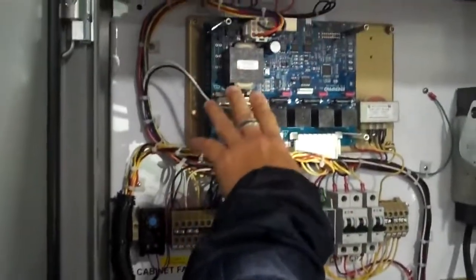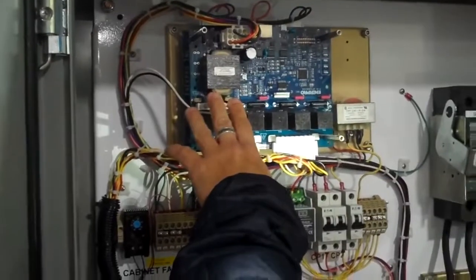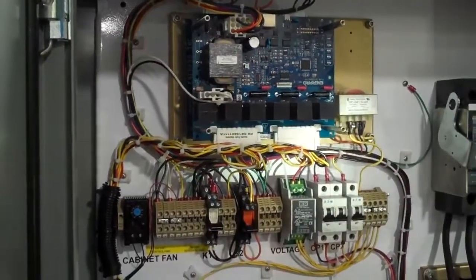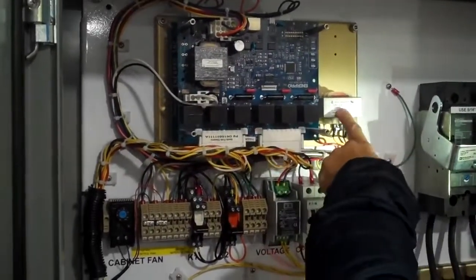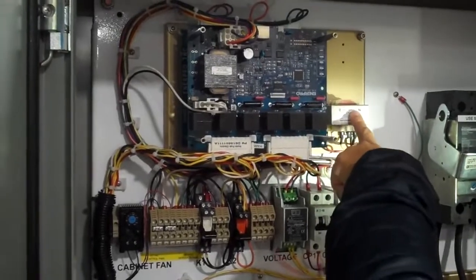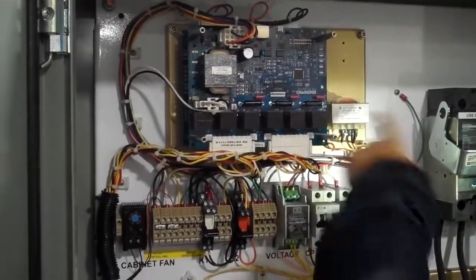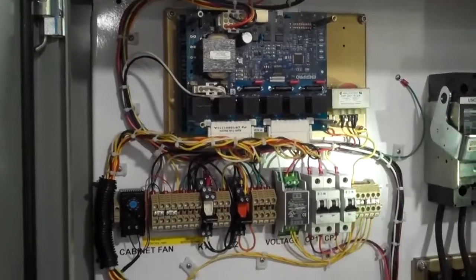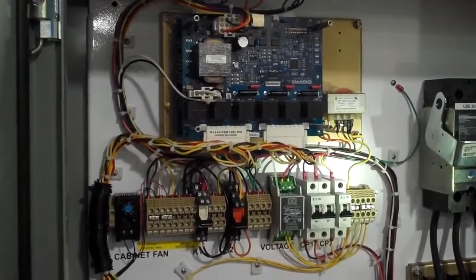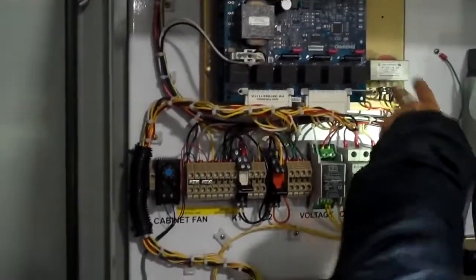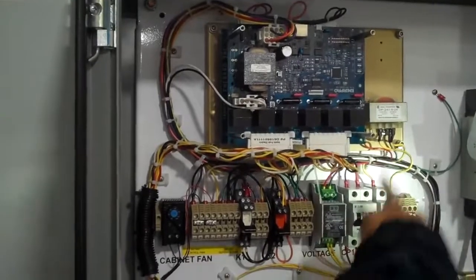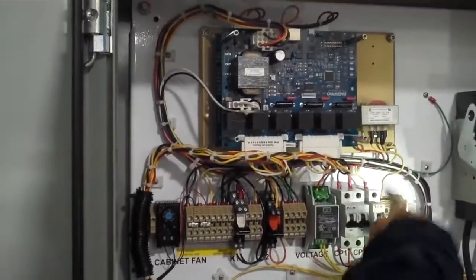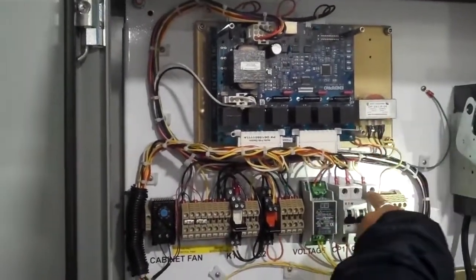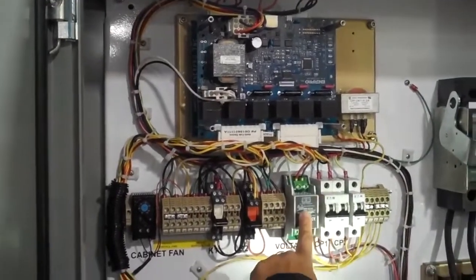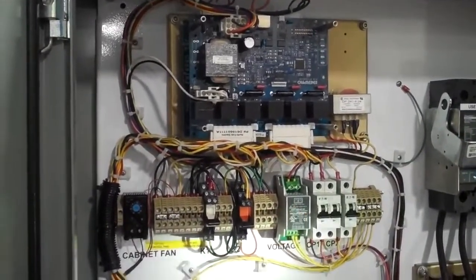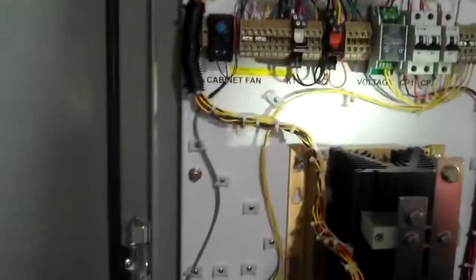We have a transformer that is powering the 120, and we also have a transformer that is picking up the 208 from the breaker, from the fuses, from the contactor. We're picking up here, and it is protected on its input and it's protected on its output. This provides the 24 volts AC to power the voltage transducer and the current transducer.